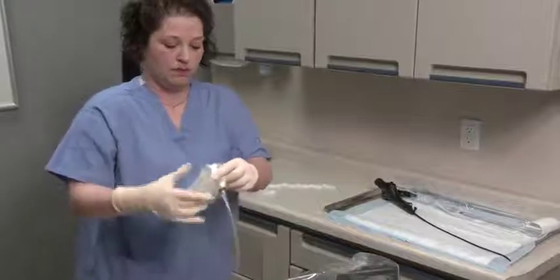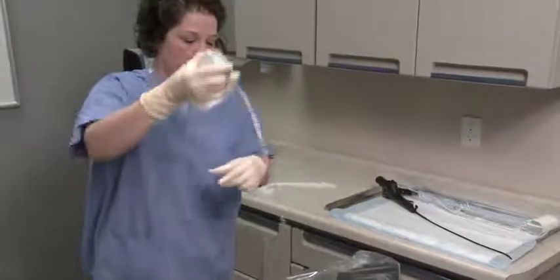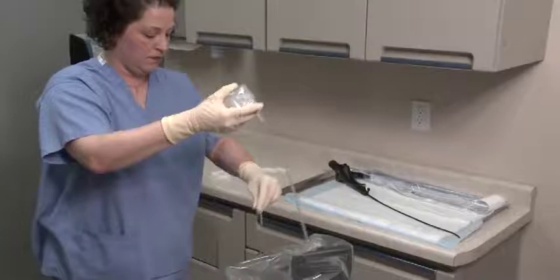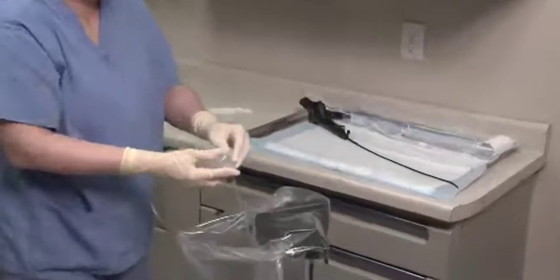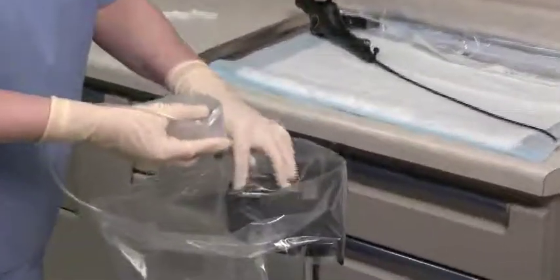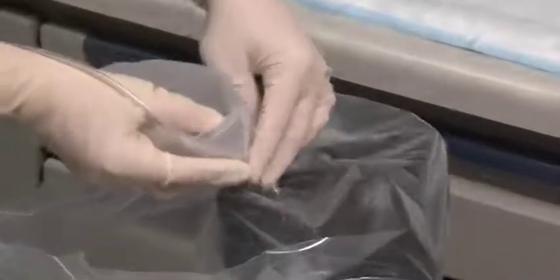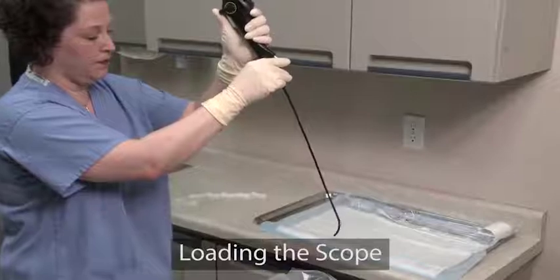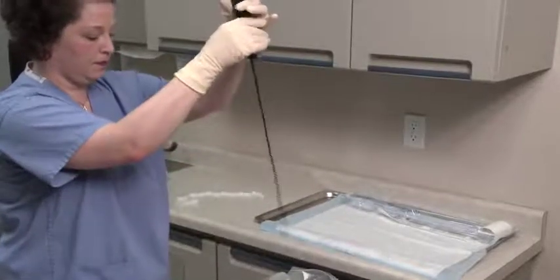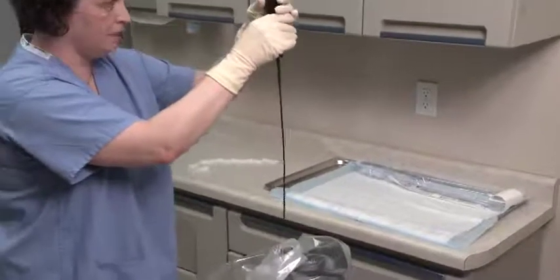Place the sheath into the installation stand. The sheath must be placed into the stand with the accessory port facing toward you. Note, the sheath fits in the stand in only one direction. Fold back the control body cover to expose the top opening of the EndoSheath connector. Before inserting the cystoscope into the sheath, it is important that the articulating distal end of the scope is straight or in the neutral position.